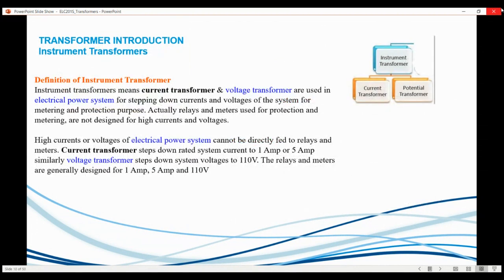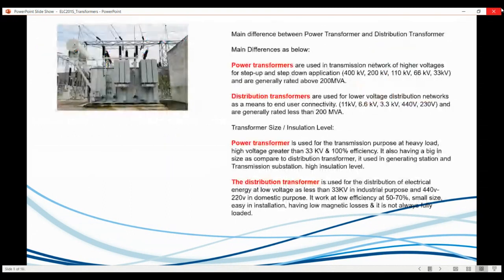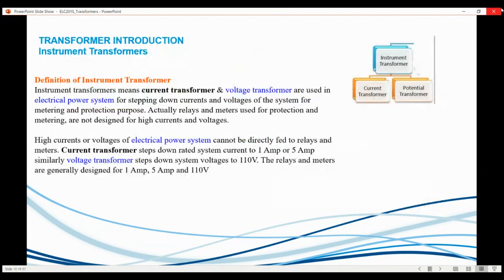Now, I'm looking at the instrument type transformers. We typically focus on these transformers, but I'm making you aware of these transformers. An instrument transformer is basically of two types: your current and your voltage transformer, and they are actually used for metering and protection purposes. We can't have a 1,000 amp circuit breaker or relay of some sort. It's impossible, or a massive protection device.